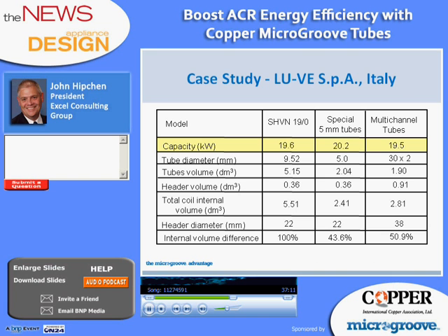Although this is yet another completely different study, at this point you can probably pick out the important factors here rather quickly now. The column that's labeled SHVN 19/0, that represents their original design, and we see that the 2 optimized designs match the cooling capacity rather nicely, all right around 20 kilowatts. Their existing coil had 9.52mm tubes, and in the trial designs, they used aluminum multi-channel tubes and 5mm copper MicroGroove tubes.